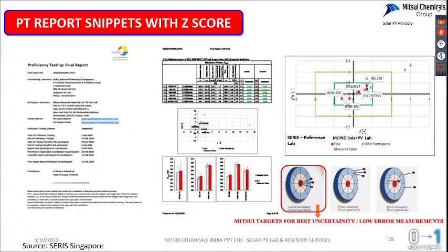That is one thing. Now related to lab errors. So far we have discussed material related errors and power plant O&M related errors. Now lab errors: being a new startup lab, first of all we have validated our measurements. We have undergone PT with SERIS Singapore, and we have verified where we are standing. You see all the measurements are very precise, concentric and in the middle of this bullseye kind of thing. Generally PT is more sophisticated than interlab comparison, which gives both Z-score and EN score, which are important reliability and performance indicators for a lab.